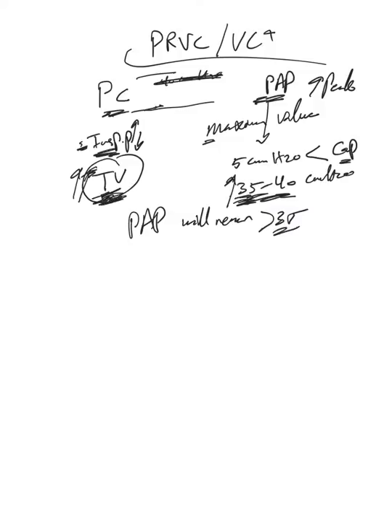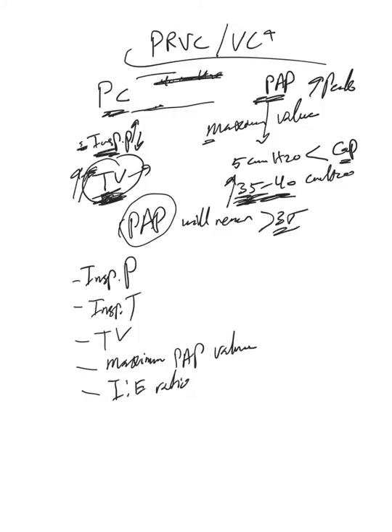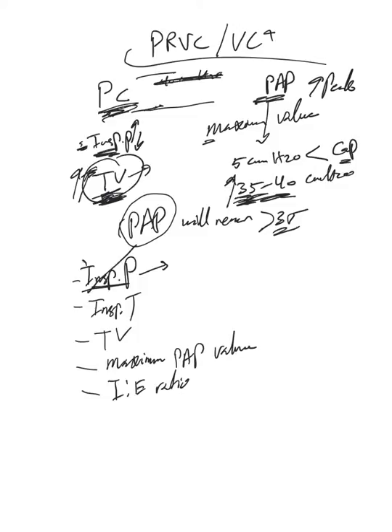We prevent and don't have to worry about the increased peak inspiratory pressure and guarantee a tidal volume. So what values do we need to provide? As I said, the inspiratory pressure, because it's a kind of pressure control target. But believe it or not, we can get rid of this.